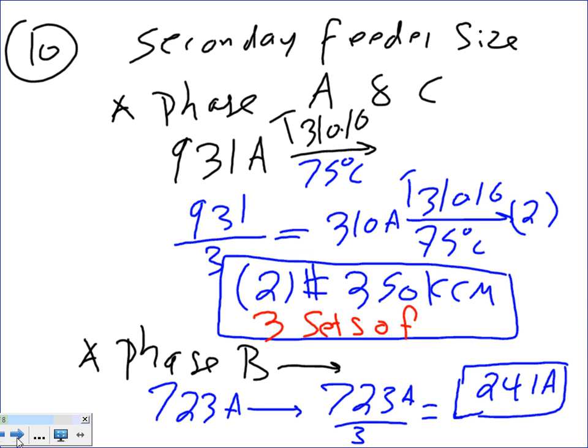You end up with a bigger conductor. But yes, you can. Or you can divide it by 4, as long as you can't parallel less than 1 aught. If you divide one by 4, you have to divide the other. Yes, you have to do it all the same. Thank you. Yeah, I see your point. If I decided to go 3 here, I have to go 3 here because we're parallel. Yep.